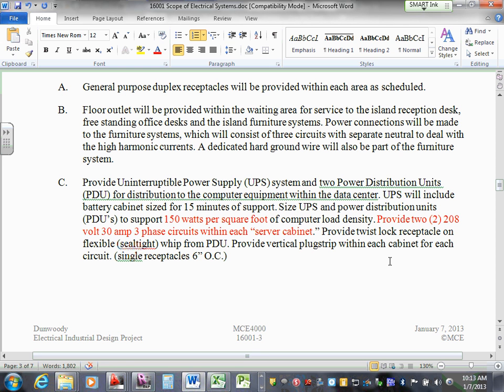Does it need to be converted to volt amps to estimate? Good question. In our world, computer equipment has a power factor of about 0.98. It's not technically the right thing to do, but on our computer floor at 150 watts a square foot, when talking to owners and IT guys, they don't know what a volt amp is, so they understand watts. When we translate that into power on the floor, we know it's really a volt amp. There is a clear distinction between watts and volt amps, no doubt, but we have a high power factor load, so the reality is it's virtually the same on the floor.